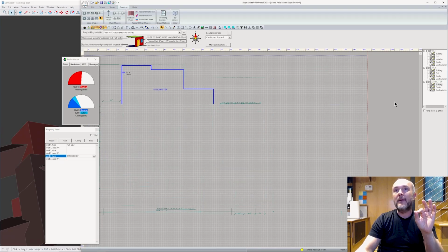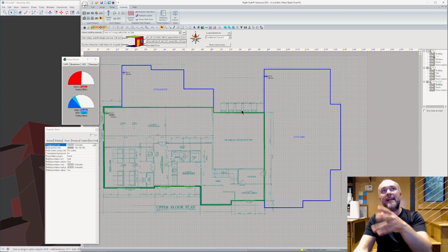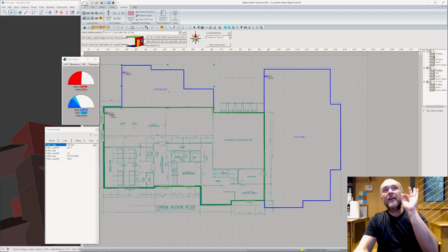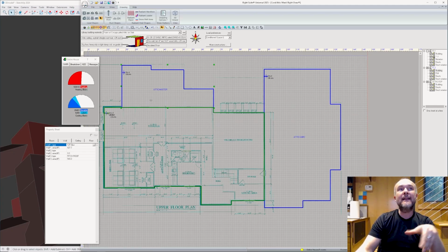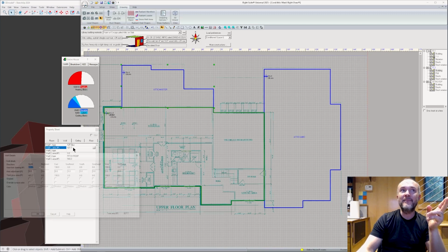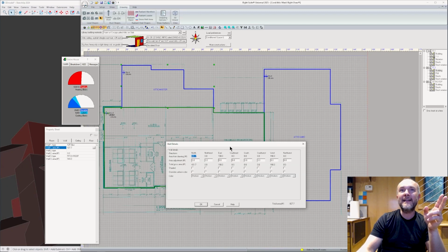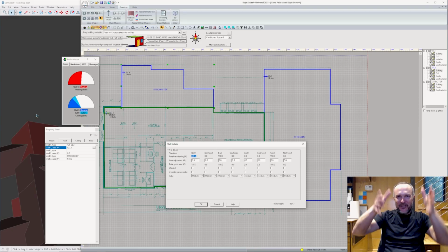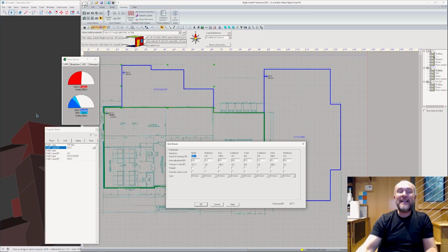Okay, so now I'm going to go ahead and add the surface area of the walls to the attic. Let's just go back. Before we leave this attic master, we're not done quite yet, and here's why. You can see that in the wall area, I have wall 1, which is 827.7 square feet of total wall area, and that's not correct anymore because it's thinking that my whole room is a cube that's 8.9 feet tall.